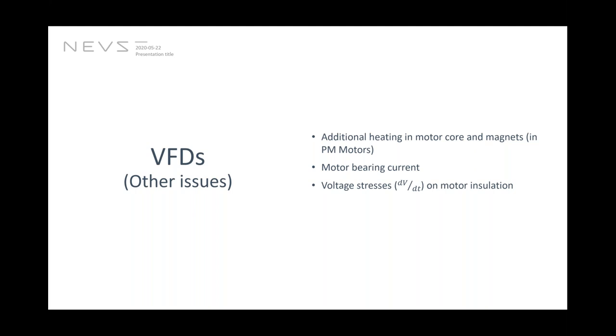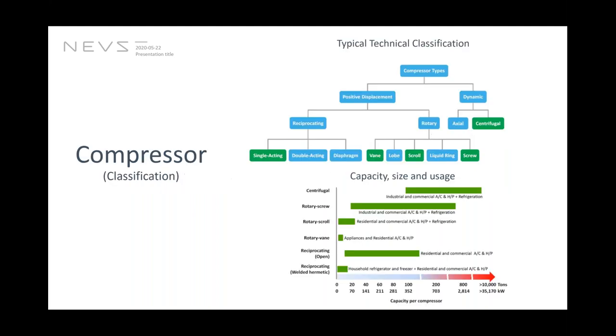As we are switching very fast, the rate of rise of the voltage is quite high in the VFD application, so we need to be careful with that as well. I found a term called inverter duty rated motors. What this means is whether your motor is inverter duty rated or not, considering these effects. So if we are trying to implement a VFD in an already existing system, we have to be careful in doing that. Now the next topic was to look into the compressor.